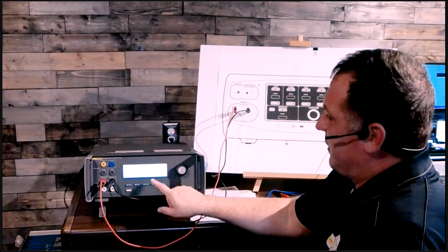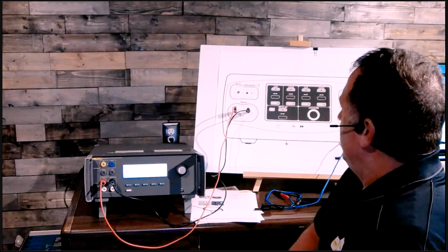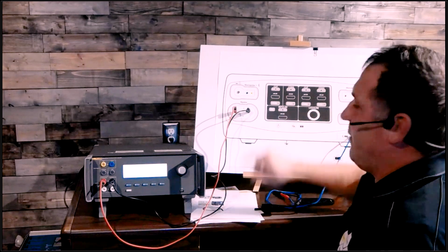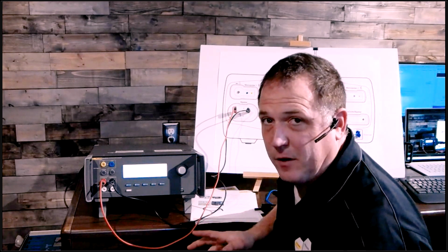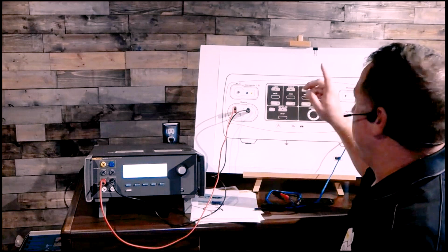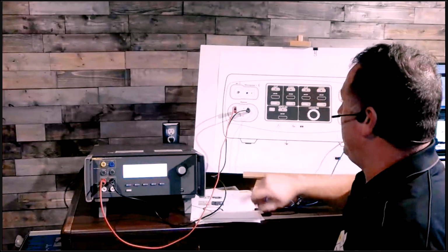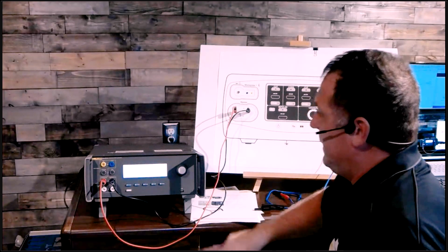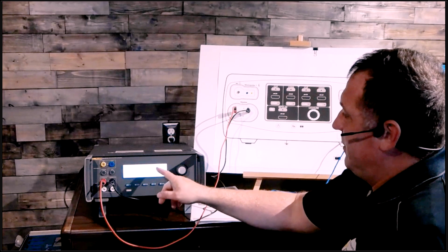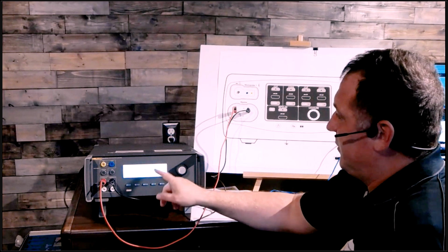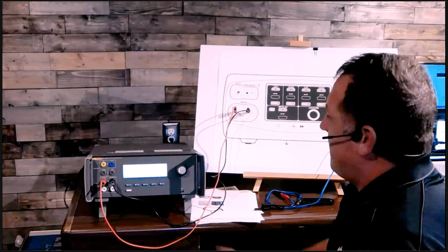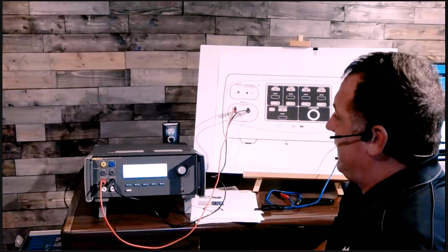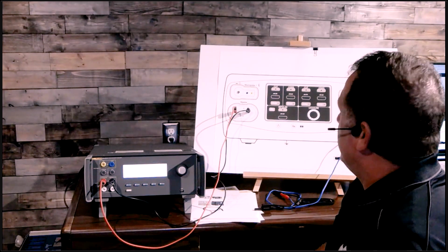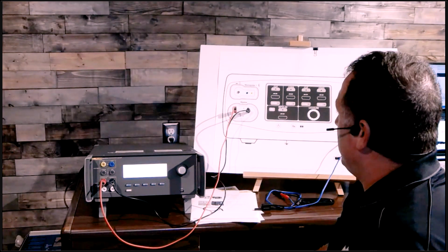Now, all I'm going to do is hit start continuous on my QES3, turn my bipolar to wherever I want it to be. Again, reference your service manual for your ESU, use my foot pedal and activate bipolar. And I get my power, my wattage, and my peak voltage right here in my QES3. And then press stop, and that ends the test. So that is nice and straightforward.